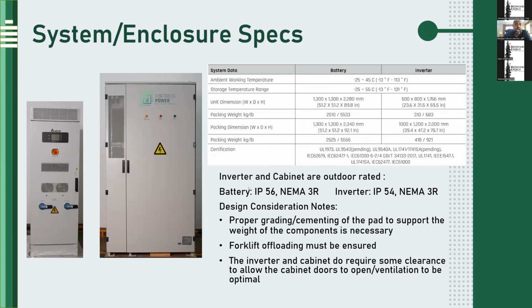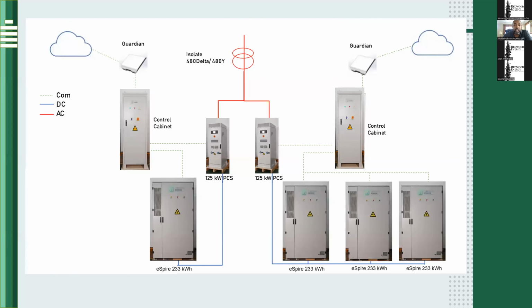Again, this is just a high level overview, and I'm going to go to the last slide. This is what a system would look like for us. It's not a full one line, but this gives a pictorial representation. The cabinet here is the inverter, that's the 125 kW inverter, and inside of here there are 3 DC bus connections. So you can take 1 cabinet to 1 inverter, or you can take 3 battery cabinets and connect them to 1 inverter. The maximum amount of battery cabinets on an inverter cabinet is 5.